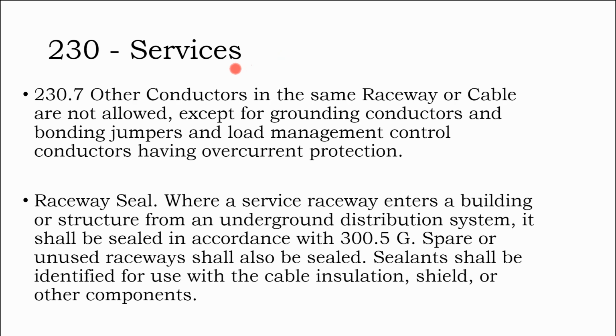For instance, here in 230, we're talking about service entrance conductors, not just feeders, but a specific kind of feeder, just the services supplying the whole building. And it says, in the raceways of service conductors, other conductors are not allowed except for grounds and other kinds of devices that have to do with load management and load control.